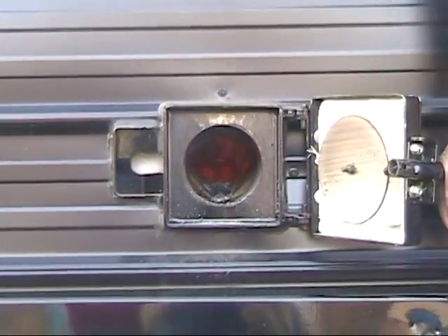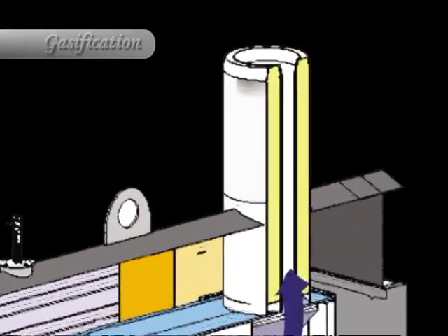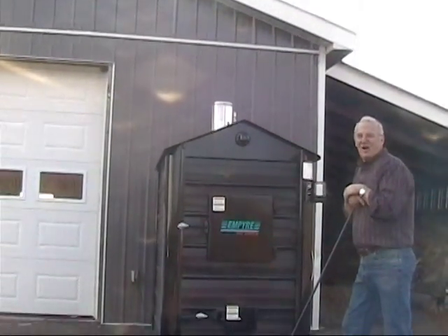After the gases are burned off, the hot air vents through a series of flues running through the water jacket. Here, heat is transferred to the water, which is used to heat your house or other buildings. By the time the air exits the chimney, it has cooled to between 300 and 350 degrees Fahrenheit.